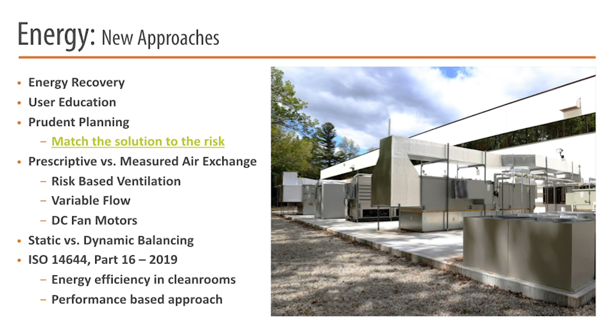There's a phenomenon now called risk-based ventilation. When you do your risk assessment, you know how many air changes you need, as opposed to a straight 12. Updates to the ISO standard for clean spaces move away from the prescriptive chart I showed earlier defining air changes per hour for each space. We're moving toward an evidence-based, performance-based approach, and we'll show you some tools we've used for that.